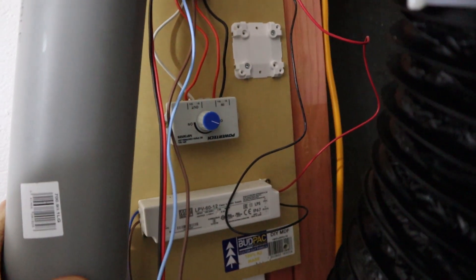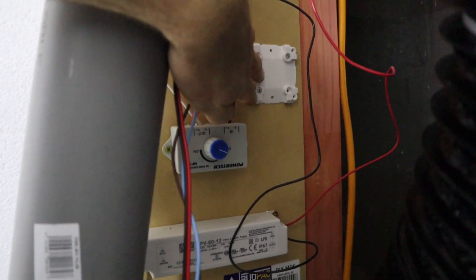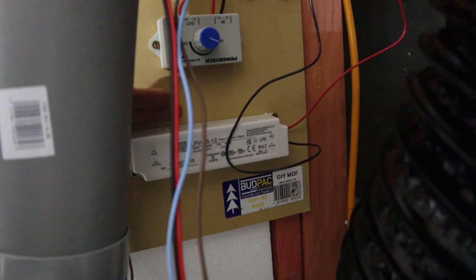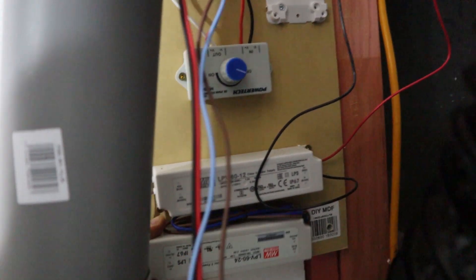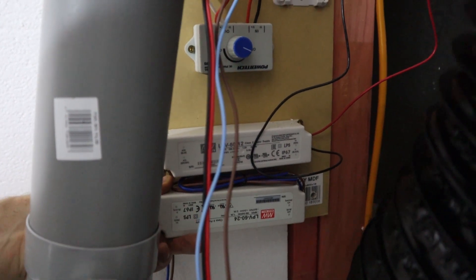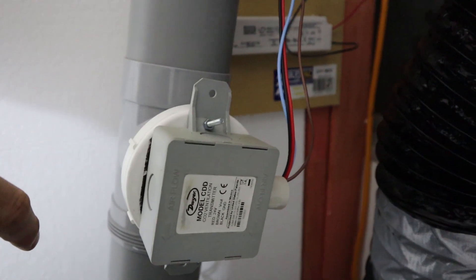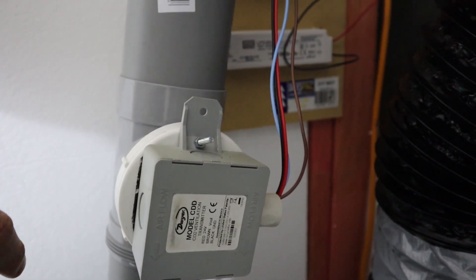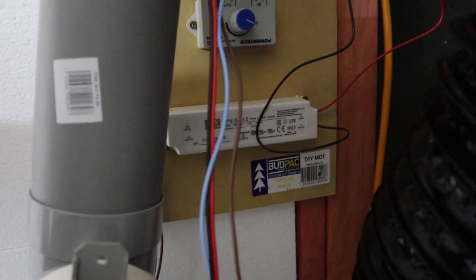This is my little ventilation control board over here — sorry it's kind of tucked into the corner. I'm going to put a termination block where the power comes in. This is a 12 volt power supply and right next to it is going to go my 24 volt — so two Mean Well power supplies. The 12 volt powers the fan which pumps air down the column, and the 24 volt is for the Dwyer transmitter, which needs 18 to 30 volts, so 24 it is.